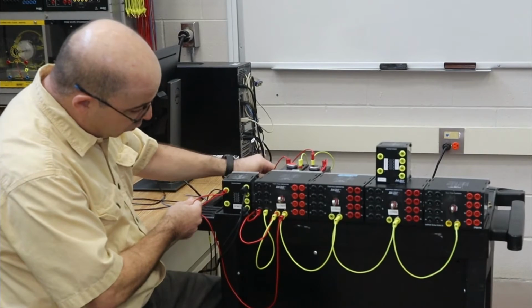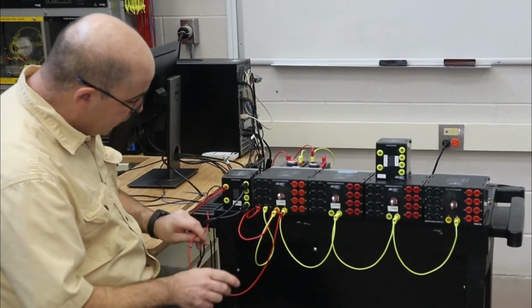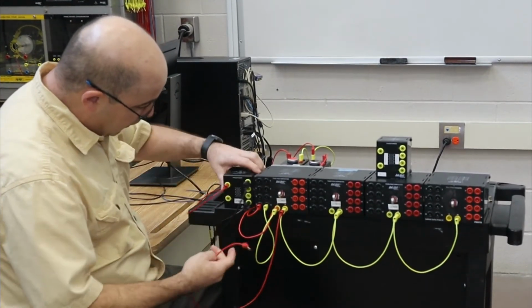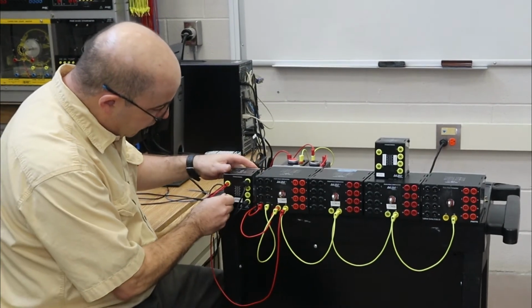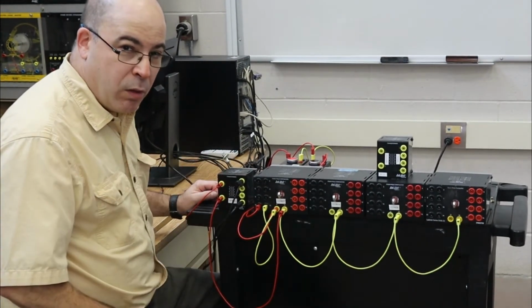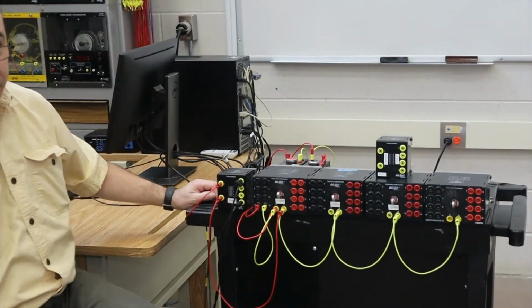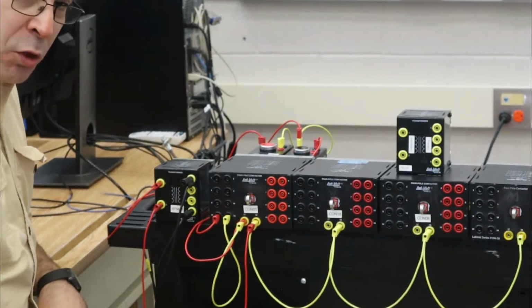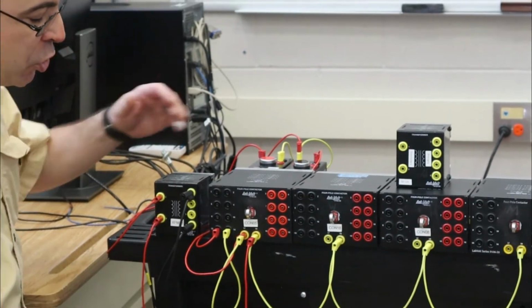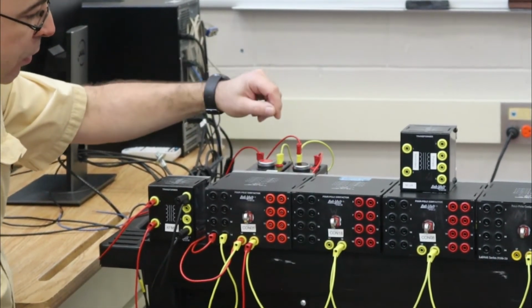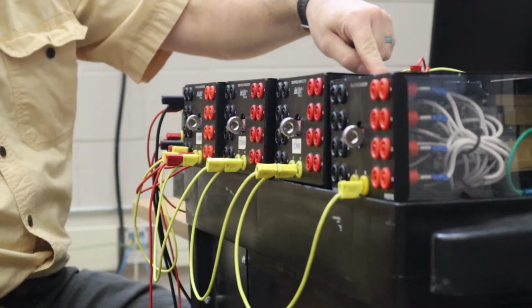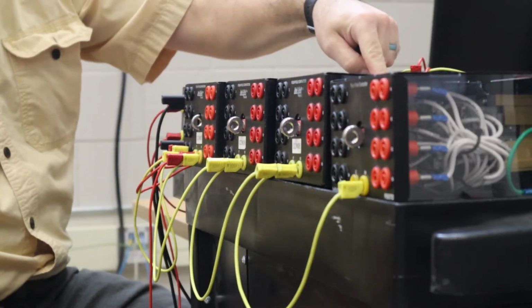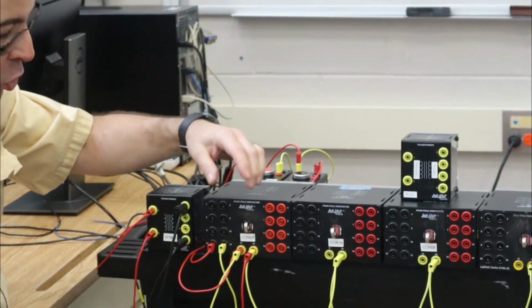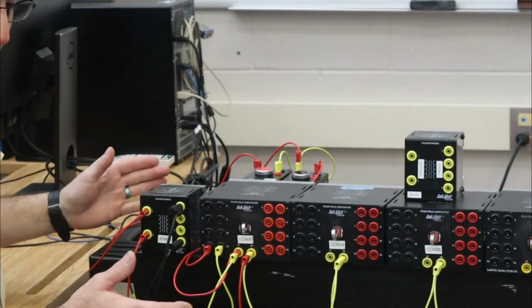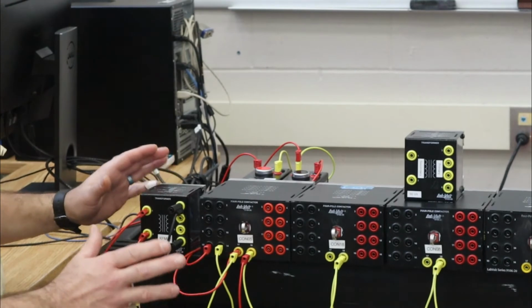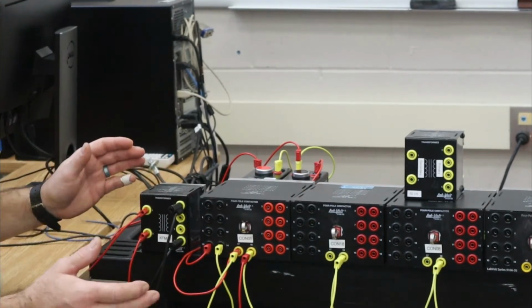Go into my control station, and I'm going to complete the circuit by going to X2. And I'm just going to go and power up my power supply. We now have control power, and I'm going to proceed to energizing the first relay. So here it goes. With a single relay on my control circuit, I depress the start button, and we can see that the armature has actually pulled in. You're not going to pick up that there's any noise whatsoever. Everything is working the way it should.